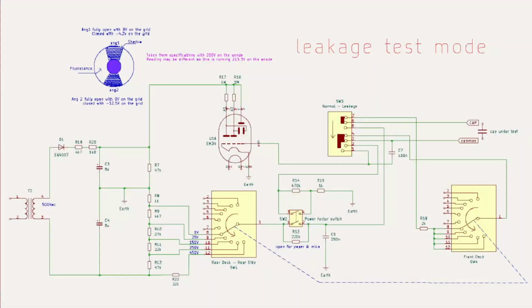Right, here we are. This is the circuit stripped out so that it's just showing the connections required for testing a cap for leakage. Nothing else. All the other parts you see are blank. Let's start looking at what we know. We have a transformer. Paperwork says it's 500 volts AC. So what do we know about that? Well, we know that the 500 volts AC gives us a reading of 707 volts peak, which is what we'll be seeing on here.